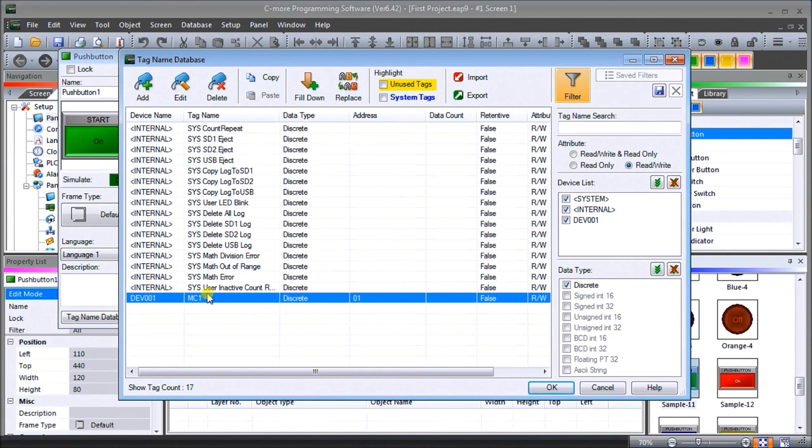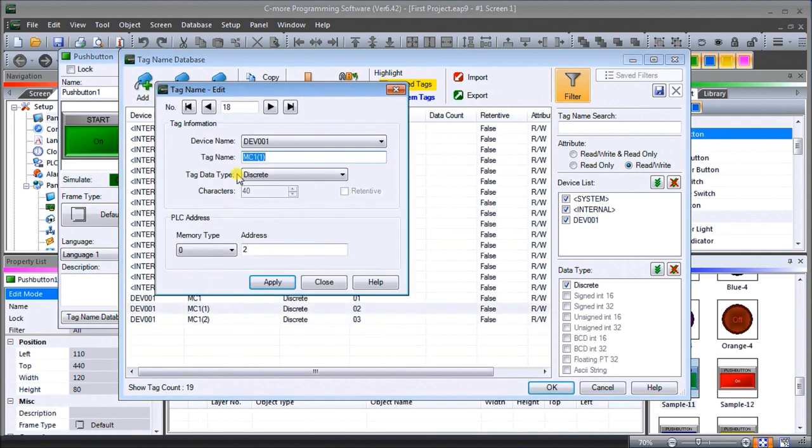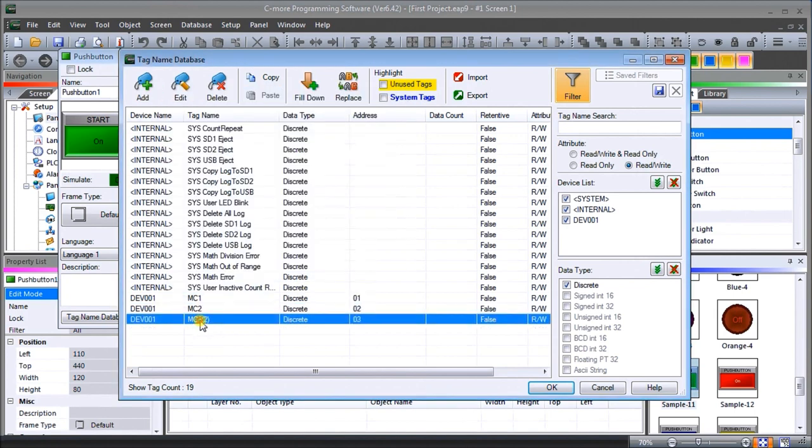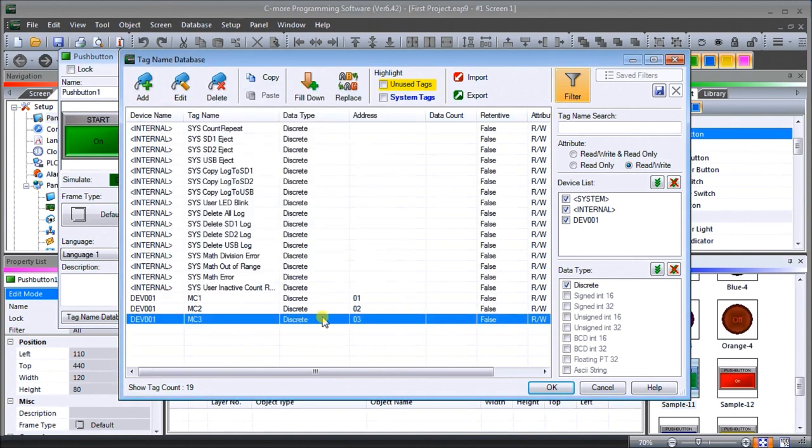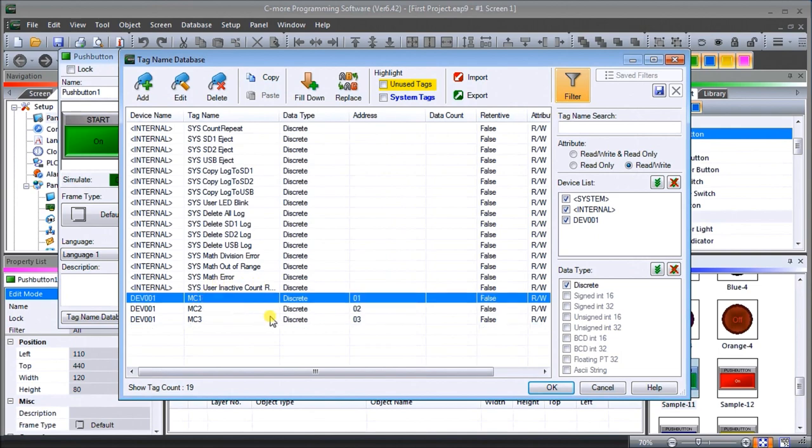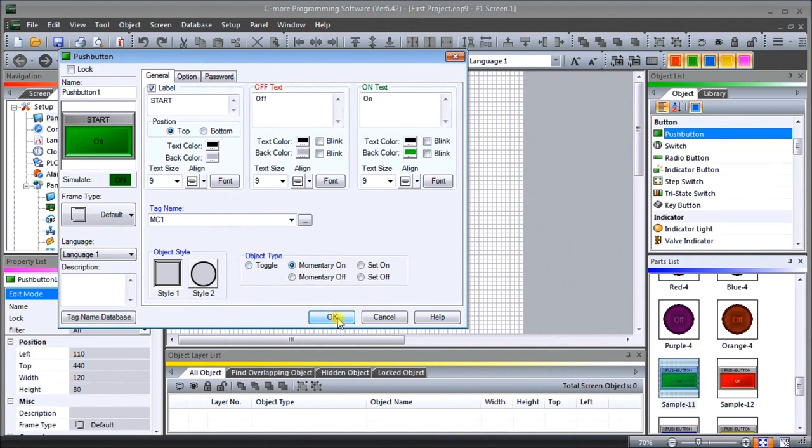It automatically will go to the next one. We'll take Close now. There's our first memory that we'll use for our start. We're going to use the fill down and we're going to add two more, then we can go back here and correct the name. This will be MC2, and this will be MC3. There's my three tags. Now we'll go back to MC1 and hit OK. That comes down here and our object type will want a momentary on, just as our PLC logic is. We'll set OK.